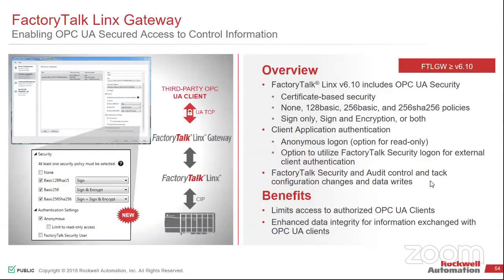So when we tie that in, the newer version, version 6, now made it so we can do OPC UA natively. So from an HMI point of view, if we're looking at FactoryTalk View SE, I can now bring in OPC UA data directly into the HMI as a function. The FactoryTalk Linx Gateway now gives me the ability to be an OPC UA server and send data out somewhere else.